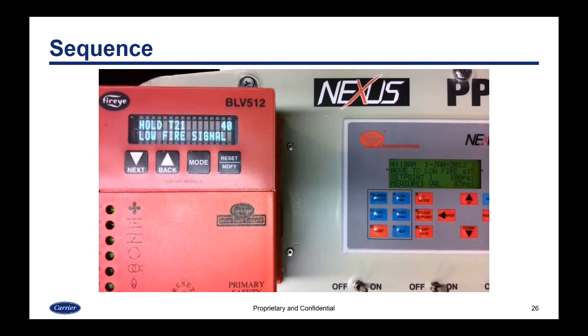So right now I'm trying some of the other options that the Burner Logix has, and this is T21, which is a terminal for low fire hold. So if you apply that terminal, it's going to go to low fire, and it's going to send the PPC to low fire. And the next one we're going to check is revert to pilot, which is terminal 16 on this particular program, or the 138.